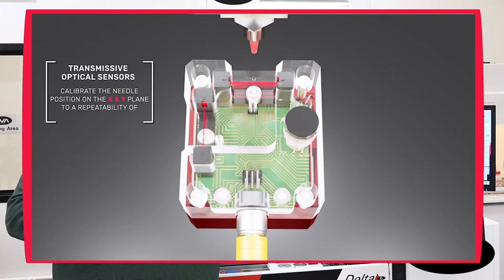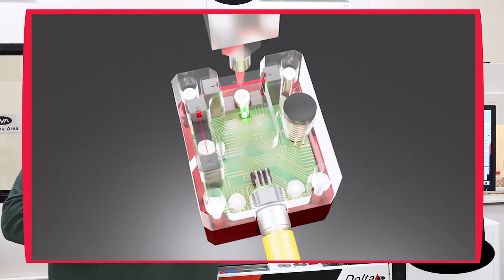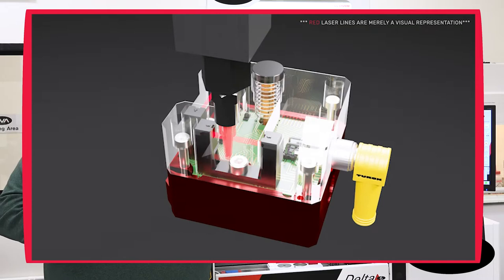Transmissive optical sensors calibrate the needle position in the XY plane to a repeatability of 50 microns. Z height detection is repeatable to 25 microns.